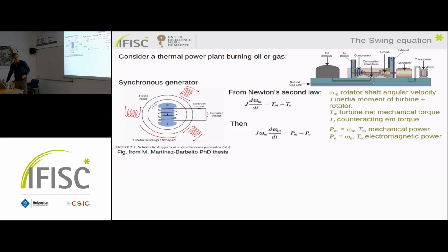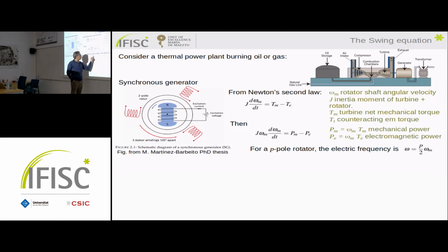If you have a two-pole rotor, the electrical frequency equals the mechanical frequency. Sometimes rotors are made to rotate at a slower frequency by adding more than 2 poles. Then the electrical frequency equals the number of poles divided by 2, multiplied by the mechanical frequency. You want this close to 50 Hertz, so depending on the number of poles, you design your system for the required mechanical power.